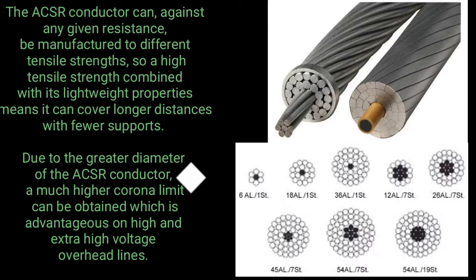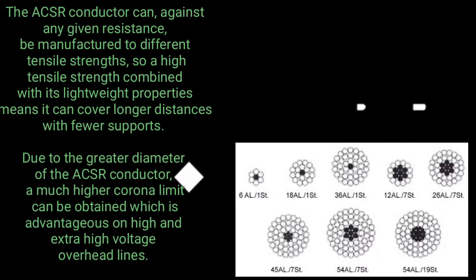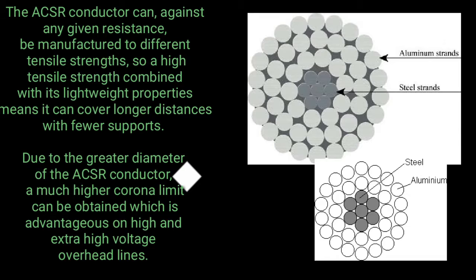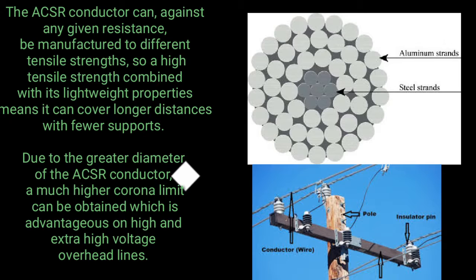The ACSR conductor, for any given resistance, can be manufactured to different tensile strengths. High tensile strength combined with its lightweight properties means it can cover longer distances with fewer supports. Due to the greater diameter of the ACSR conductor, a much higher corona limit can be obtained, which is advantageous for high and extra high voltage overhead lines.